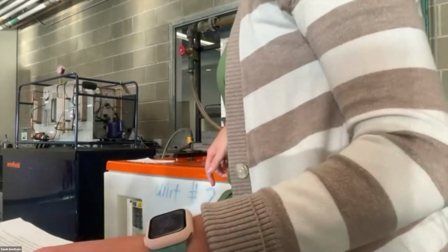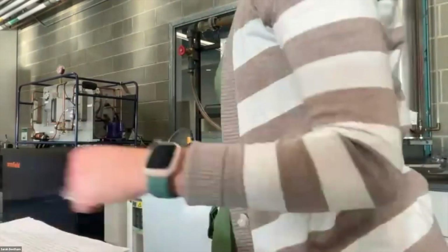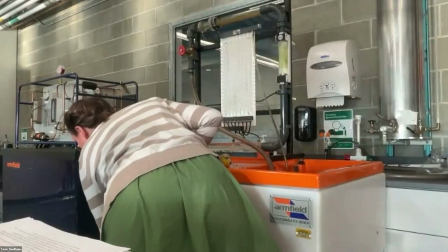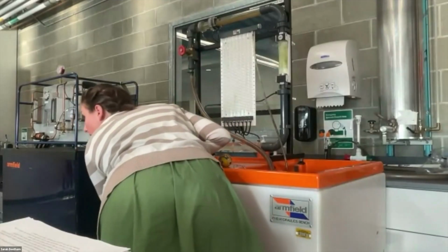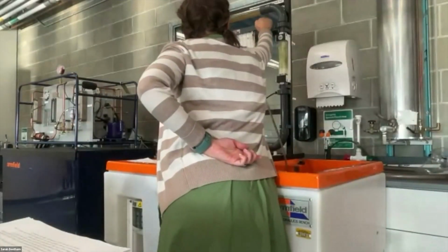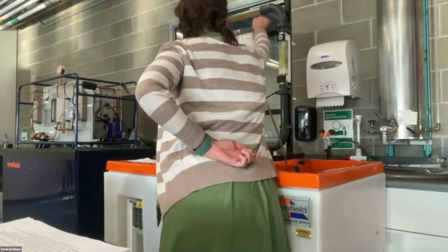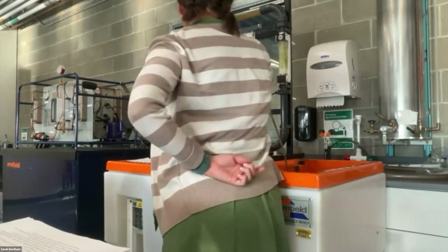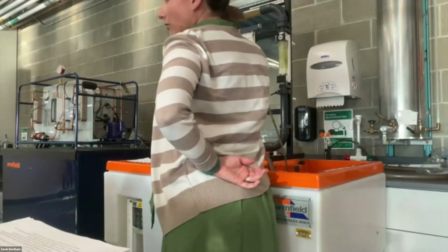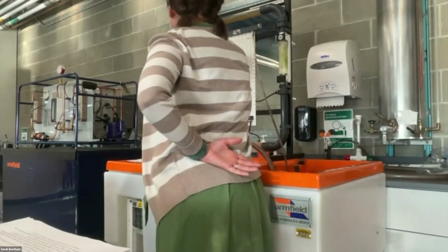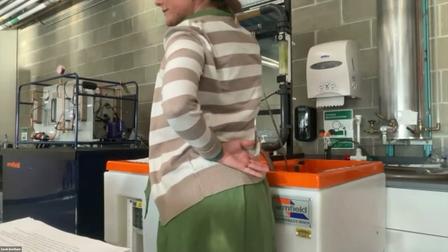And next, we're going to turn off the flow from the bench. So we're going to tighten the blue knob and then purge out any bubbles that we might see on the manometer. And the idea is to get your manometer to about this level, so like halfway. And the reason for that is when the pressure increases, we don't want the manometer to be overfilling, right?